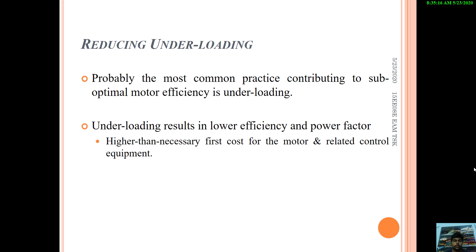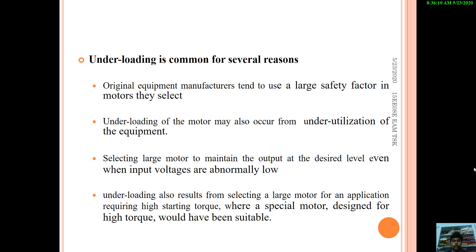Underloading is common for several reasons. Original equipment manufacturers tend to use a large safety factor in the motors they select. Underloading of the motor may also occur from underutilization of the equipment. The third one is selecting a large motor to maintain the output at the desired level even when input voltages are abnormally low; a large motor operating under low voltage will cause underloading. Underloading also results from selecting a large motor for an application requiring high starting torque, where a special motor designed for high torque would have been suitable. These are the major reasons that cause underloading.